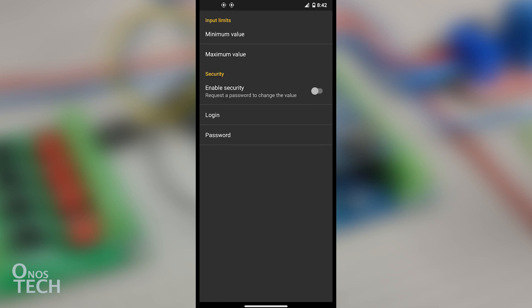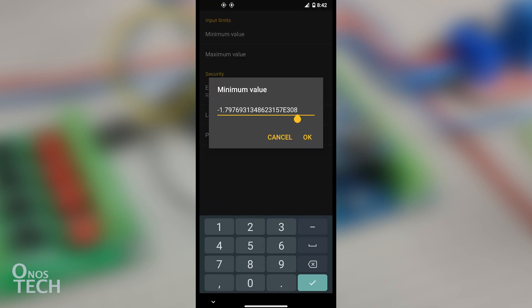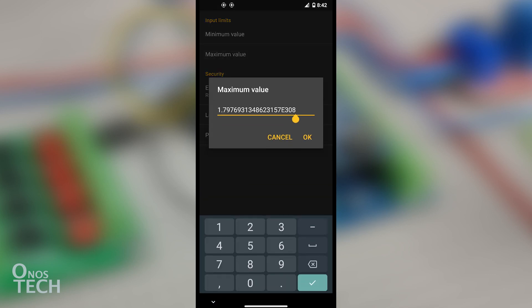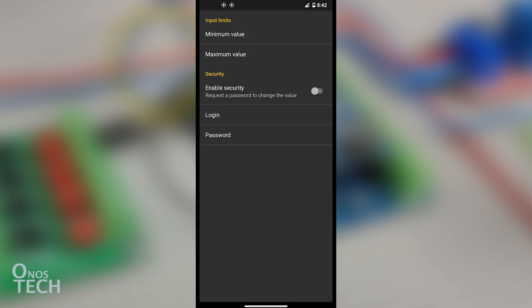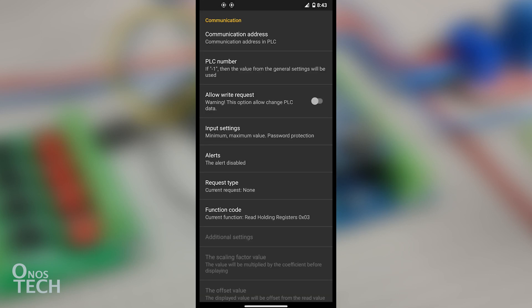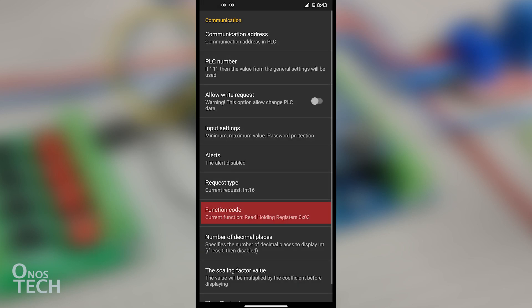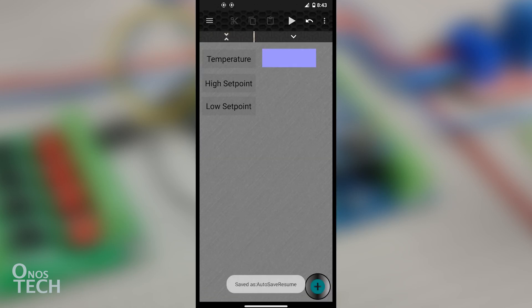Select Input Settings. Change the Minimum value to 0 and the Maximum value to 150. Change the Request Type to INT16 and ensure that the function code is ReadHoldingRegisters 0x03. Go to the main screen.